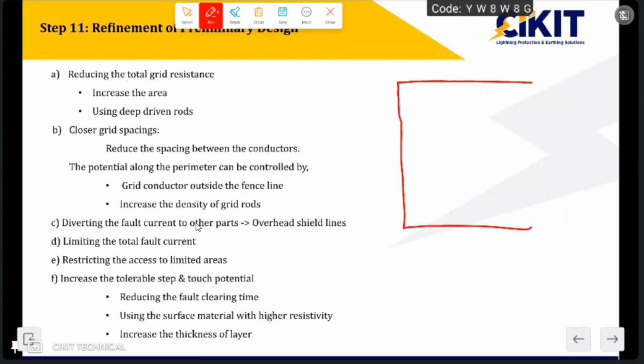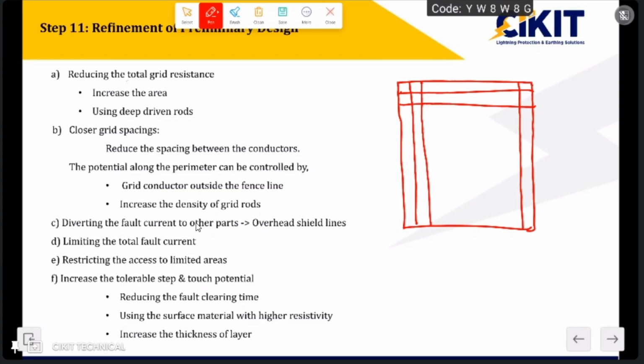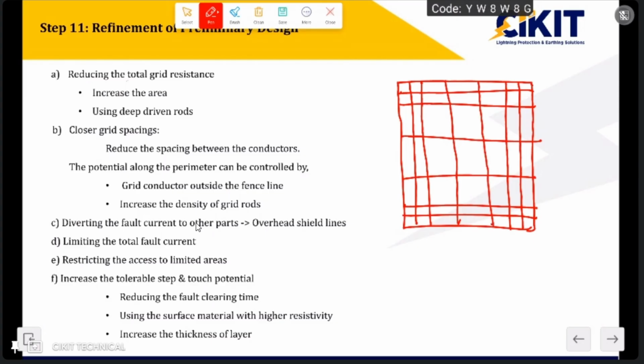So if this is the perimeter, then instead of maintaining uniform spacing for the grid, I can provide very close spacings near this perimeter area. So here I am maintaining very close spacing, but in the inside area I won't maintain the same. I will provide higher spacing. So the closer spacing will be maintained only at this perimeter region, whereas in the internal area it won't be maintained. By reducing the spacing on this perimeter area, we are bringing down the voltage levels to tolerable values. So the safety of the persons on this perimeter area can be maintained by using these 3 steps.